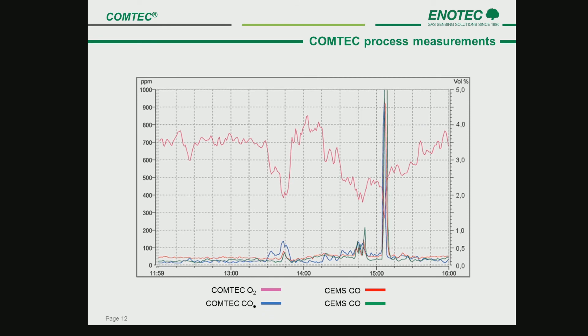The relationship between excess O2 after combustion and combustibles in the flue gas can be clearly seen. The following trends are from a black coal-fired power plant in a 600 MW unit. The installation point is after the economizer, before the air preheater. The pink trend is the Comtec O2 measurement, the blue trend is the Comtec CO measurement, and the red and green trends are CO measurements at the stack for emissions monitoring. The interdependency between excess O2 and CO values can be clearly seen — as soon as the O2 concentration drops, an increase in CO can be measured and vice versa. The Comtec CO measurement trends well with the stack CO measurement.